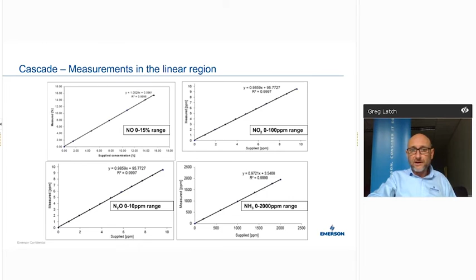As we're heading towards the end of the slide deck, Cascade, from a long-term stability point of view, works on the first principles of the Beer-Lambert law. Nothing changes in that space unless the physics change in the future, which I'm not aware of. It works on absorption, concentration, and path length. We manage all of those. The path length doesn't change with time - they're fixed and firm. The absorption properties of the gas do not change, and we've got those fixed and firm. Management of pressure and temperature is also managed within the cell and around it from the sample handling point of view, so we actually compensate for that live.